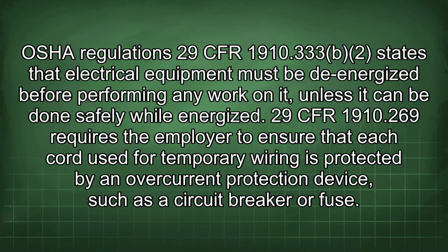OSHA Regulations. 29 CFR 1910.333 states that electrical equipment must be de-energized before performing any work on it unless it can be done safely while energized. 29 CFR 1910.269 requires the employer to ensure that each cord used for temporary wiring is protected by an overcurrent protection device such as a circuit breaker or fuse.